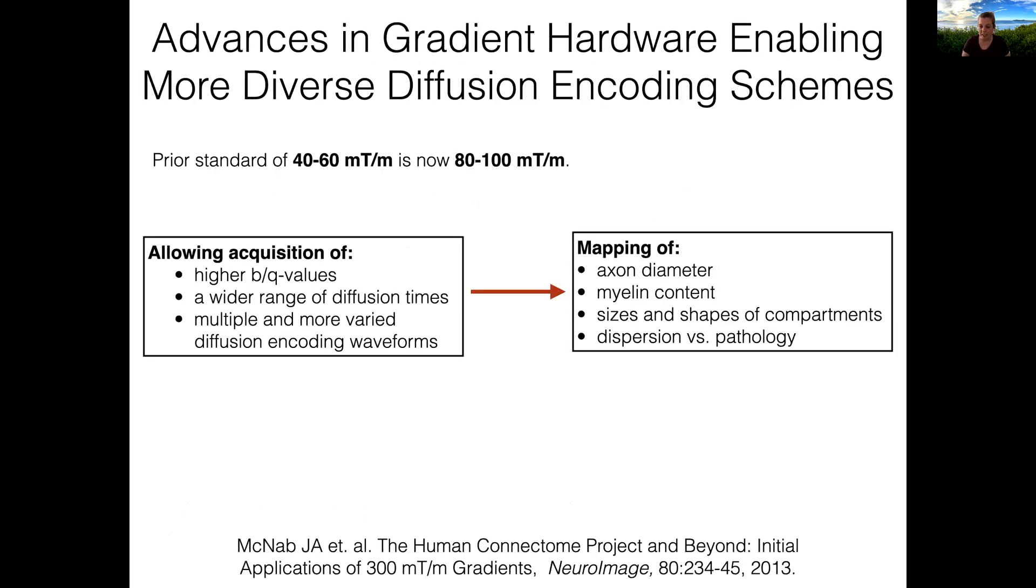Something that is enabling more diverse diffusion encoding schemes are the significant advances that have been made in gradient hardware over the last decade. The previous standard maximum gradient strength was around 40 to 60 millitesla per meter for human MRI scanners and that's increased to about 80 to 100 millitesla per meter. There are now several scanners available as a product by multiple different vendors that provide these capabilities. The ability to execute stronger and in some cases faster gradients enables us to acquire diffusion data with higher b values and q values, a wider range of diffusion times, and multiple and more varied diffusion encoding waveforms.